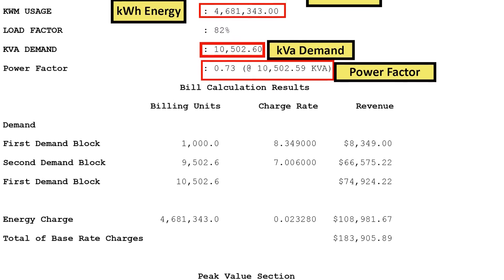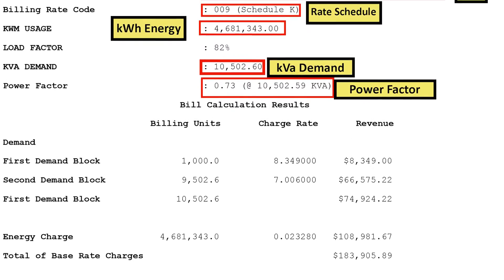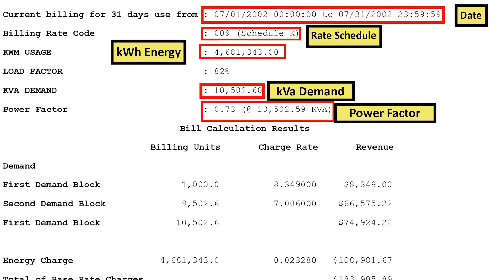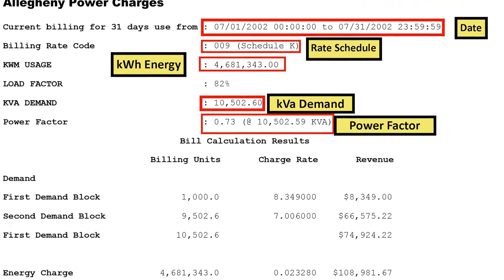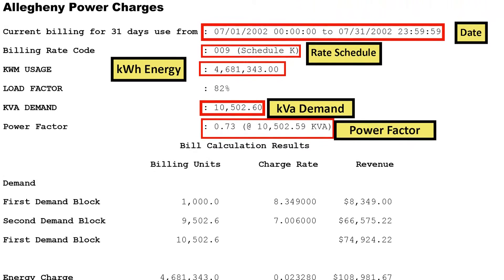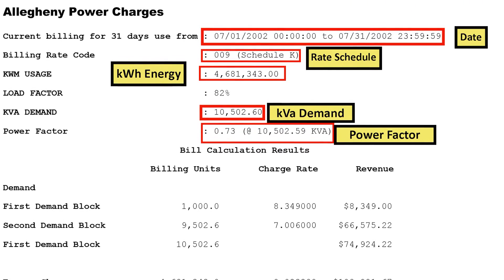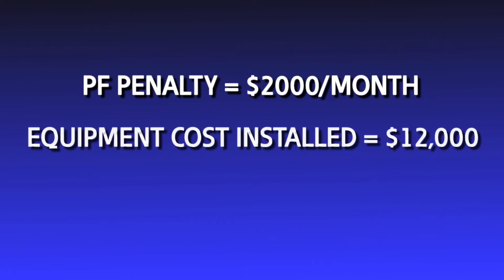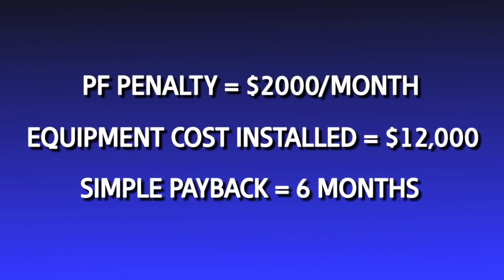Utilities bill for kilowatts and kilowatt hours, but in some cases they will penalize large commercial and industrial customers if their power factor is low — in other words, if they waste KVA capacity using a lot of reactive power. Applying power factor correction is an easy way to reduce or eliminate these penalties. If a penalty is imposed, the payback may be as short as 6 to 24 months.